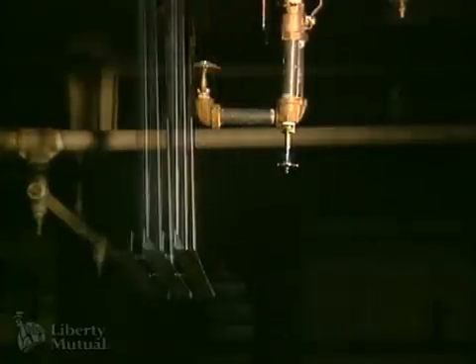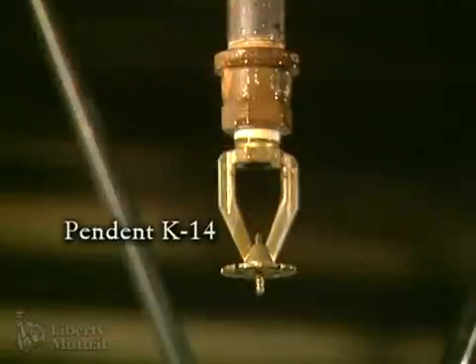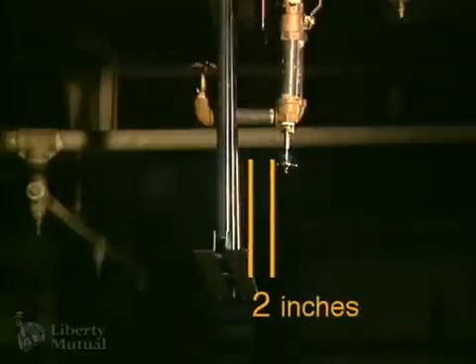This testing will try to visually demonstrate the relative severity of the obstruction based on various horizontal distances to the ESFR sprinkler. Our first demonstration is to position the edge of the bottom chord of the bar joist about 2 inches away from the edge of the ESFR deflector.